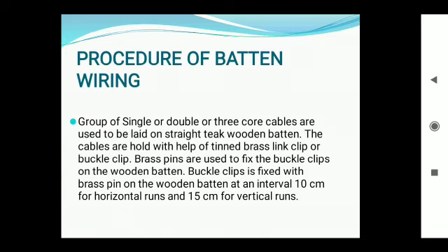Now the procedure of batten wiring: a group of single, double or three core cables are laid on a straight teak wood batten. The cables are held with the help of tinned brass link clips or buckle clips. Brass pins are used to fix the buckle clip on the wooden batten. Buckle clips are fixed with brass pins on the wooden batten at an interval of 10 cm for horizontal runs and 15 cm for vertical runs.